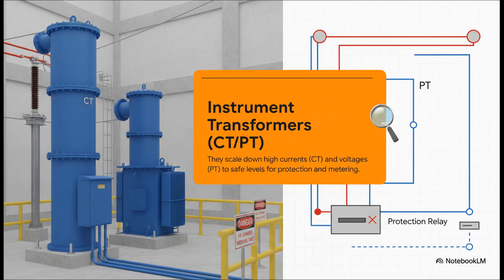So how does the system even know when something's gone wrong? Well, it has senses, the instrument transformers. You've got current transformers, or CTs, and potential transformers, PTs. They take these huge, lethal currents and voltages and shrink them down to safe, readable levels. For instance, a CT might take 600 amps and turn it into a tiny 1 amp signal that a protection relay can safely read. That's the signal that tells the circuit breaker, hey, trip now.